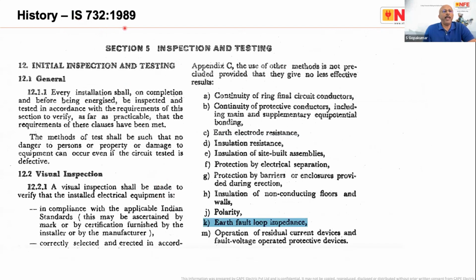IS 732 1989, section 5, inspection and testing. Of course, we don't have the habit of making an inspection and testing. That is a different case. But if you look at section 5, inspection and testing, you can see serial number K, earth fault loop impedance. There are several tests, for example, continuity of final ring circuit and continuity of protective conductors. In the new standards, A and B of 1989 have been clubbed together and written as one test: continuity of conductors or continuity of wires.